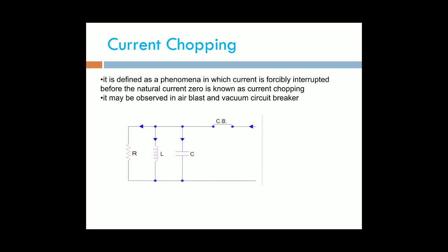Next topic is current chopping. It is defined as the phenomenon in which current is forcibly interrupted before the natural current zero. For every half cycle, the current may reach natural zero, and in that condition the arc may be extinguished. When the current is forcibly interrupted before the natural current zero, it is known as current chopping.